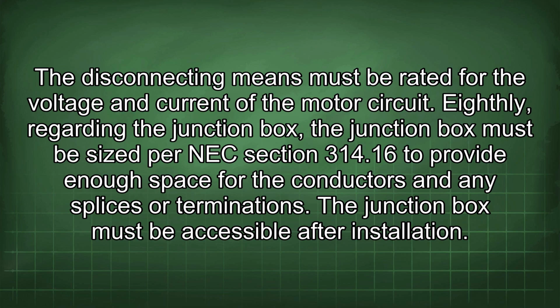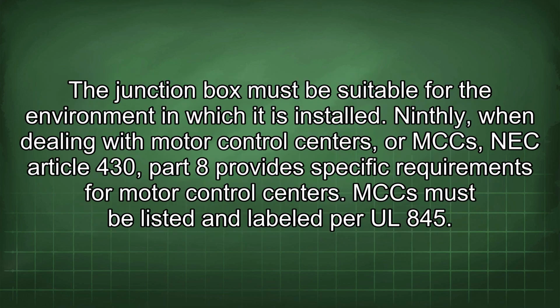Eighthly, regarding the junction box, it must be sized per NEC Section 314.16 to provide enough space for the conductors and any splices or terminations. The junction box must be accessible after installation. The junction box must be suitable for the environment in which it is installed.